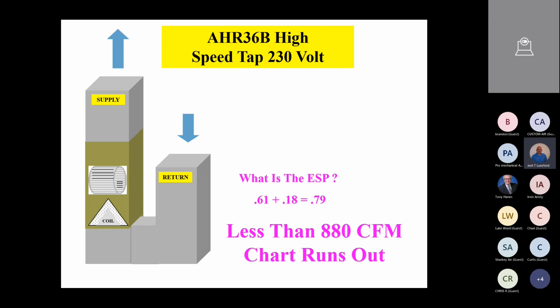because if we get in a situation and we're off of our chart, then we know that we have some remediation to do. We need to start investigating and finding out why that supply duct, in this example, maybe the TV guy was up in the attic or whatever, or something happened and the supply duct is collapsed. Or if it's on a brand new installation and you're starting the thing up, you have grossly undersized supply duct. And so please keep all that in mind right now. This is kind of part of an airflow and duct design class that we've taken out. We're showing you how to measure airflow, but it's really important that we start investigating as to why we have such high static pressure. Any questions or comments on that second example?